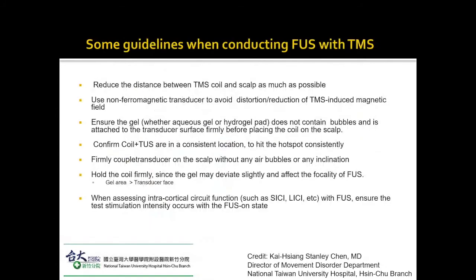A few more points: using non-ferromagnetic devices is very important, not only to reduce distortion of the magnetic field, but also to prevent damage to your transducer. Make sure you don't have any bubbles in your coupling media or in any of the relevant interfaces we talked about earlier.